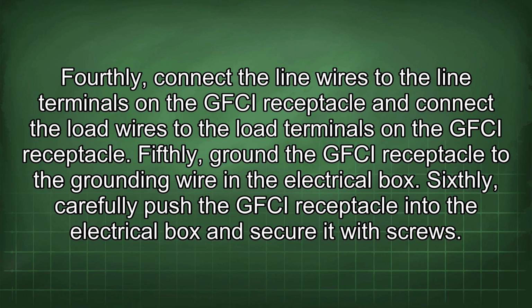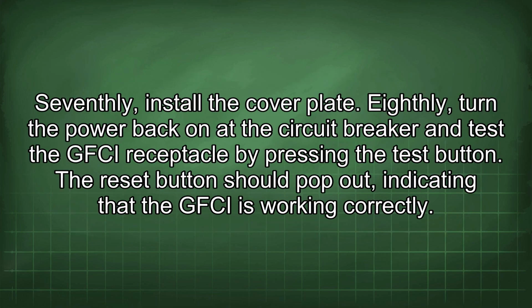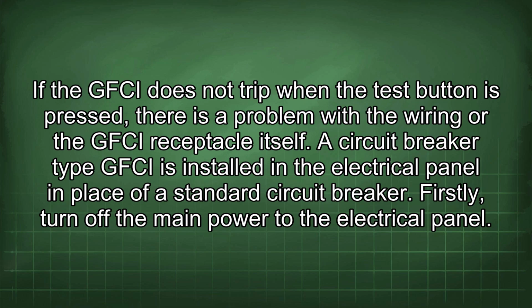Fifthly, ground the GFCI receptacle to the grounding wire in the electrical box. Sixthly, carefully push the GFCI receptacle into the electrical box and secure it with screws. Seventhly, install the cover plate. Eighthly, turn the power back on at the circuit breaker and test the GFCI receptacle by pressing the test button. The reset button should pop out, indicating that the GFCI is working correctly. If the GFCI does not trip when the test button is pressed, there is a problem with the wiring or the GFCI receptacle itself.